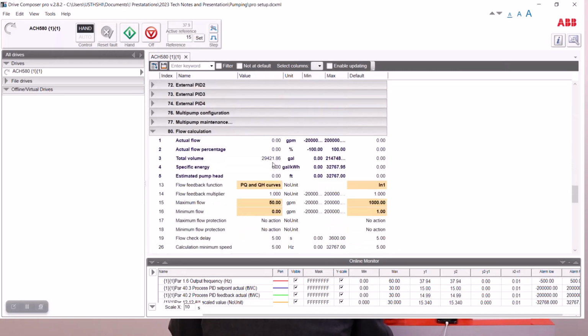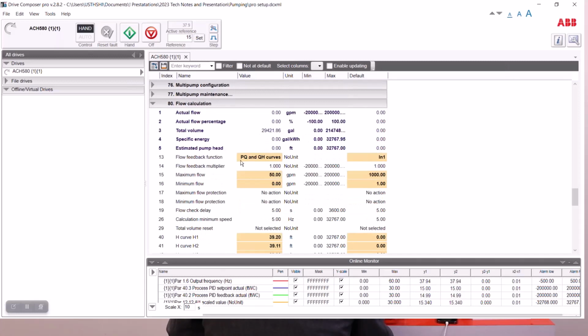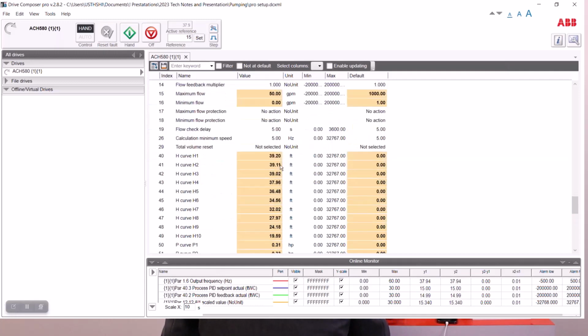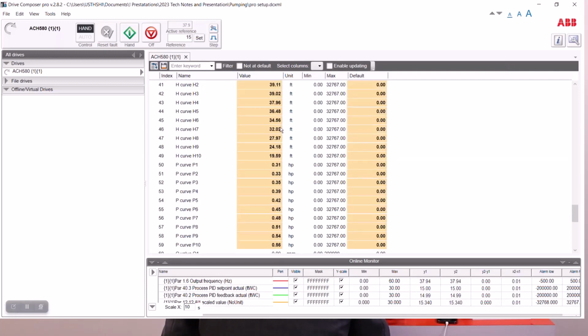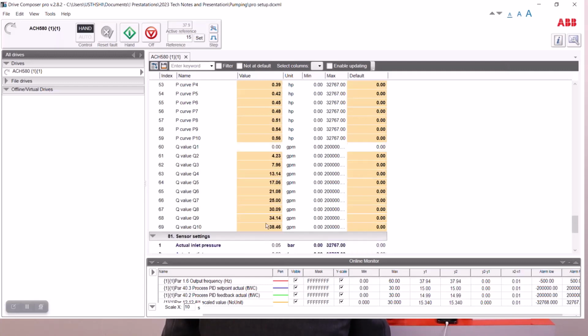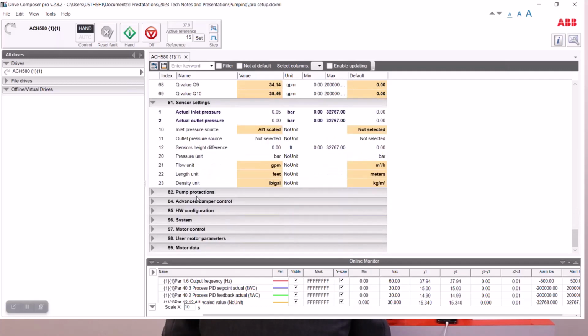Let's go down to group 80, flow calculations. Here are the flow calculations. What's happening here is I've set the P to Q, which is power to flow, and the Q to H, flow to head, curves. That's my feedback function. This had to be set up to set our data up as I showed earlier. And here's the data that we entered in: your feet of pressure, your horsepower, and your gallons per minute. So that's your H, P, and Q data. The other thing that I put in here is I've got my flow units as gallons per minute, and my length in feet.